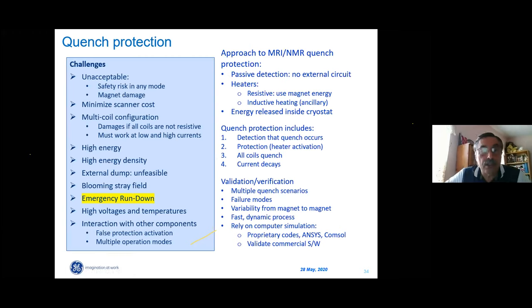We are almost done. Quench protection. Again, those magnets are installed in hospitals. Safety risk and magnet damage are unacceptable. Absolutely unacceptable. So this means that after a quench, we should be able to cool down, ramp the magnet up again, and be ready for operation within a few days. Quench protection must not be expensive. Quench protection must work at all possible currents. In multi-coil configurations, not that easy. We need to be able to detect a quench and activate quench protection in all coils, even at all currents. At the same time, high energy and high current density make it challenging.